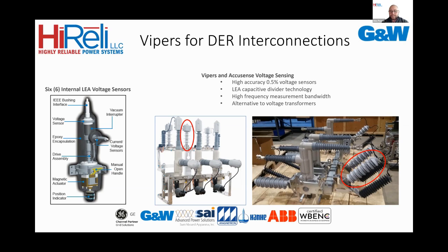So whether you're looking to sync your DER into the grid, or analyze when you might have to trip for your ride-through requirements, this higher accuracy is going to give you a little more flexibility on when you have to perform those actions. You can see they're much smaller than your traditional PTs, your wire-wound PTs. They're active, so that 0.5% accuracy goes all the way through the temperature range. Much lighter, and they can be mounted on the Viper reclosers themselves, or they can be mounted as a standalone unit.